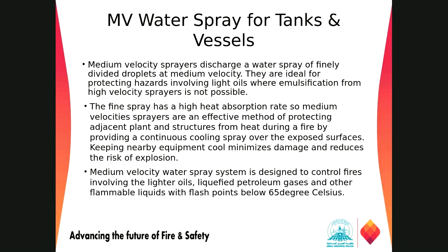So coming back from slide 9, right? Medium velocity sprays discharge water as finely divided droplets at medium velocity. They are ideal for protection involving light oil. So medium velocity is used for the light oils, where emulsification from high velocity spray is not possible. Those are the areas of application, right? The tanks, vessels, and all that we see in the process industry.